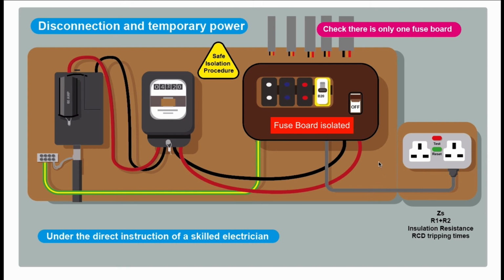So then what I like to do is, this is a kind of rewirable Wylex type board with the rewirable fuses. I often just swap it out for a B20 plug-in fuse, just in case there's any issue. It's just easier to switch that back on again than rewiring one of these. And then I'll run an RCD socket off that, just a radial off it, 2.5 radial to this socket on a B20 fuse. So we've got RCD protection. So we've got a temporary supply, so anybody in can charge the batteries, plug the kettle in, whatever they need. So this is just a temporary supply. We can improve this later down the line.